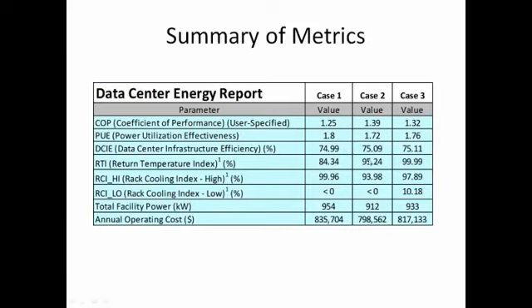metrics, RTI and RCI. And here what we see is we started off with an RTI of 84, and when we shut off the 20-ton CRAC, it went to 95, so pretty good. But when we shut off that 30-ton CRAC, things got even better. We went to 99%. But the RCI high actually got a little better as well. It went to 93 and then to 97. And then the RCI low came up to 10. So that one came up as well. So you can use these metrics as a way to drive the design, and they work quite well.